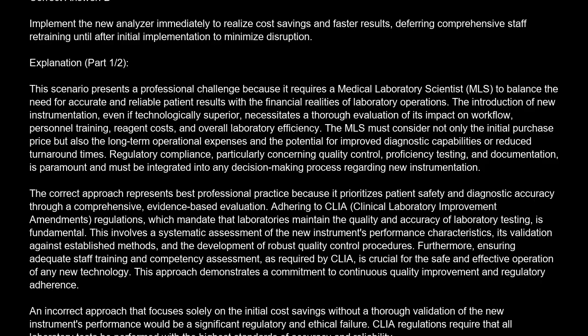This involves a systematic assessment of the new instrument's performance characteristics, its validation against established methods, and the development of robust quality control procedures. Furthermore, ensuring adequate staff training and competency assessment, as required by CLIA, is crucial for the safe and effective operation of any new technology. This approach demonstrates a commitment to continuous quality improvement and regulatory adherence.